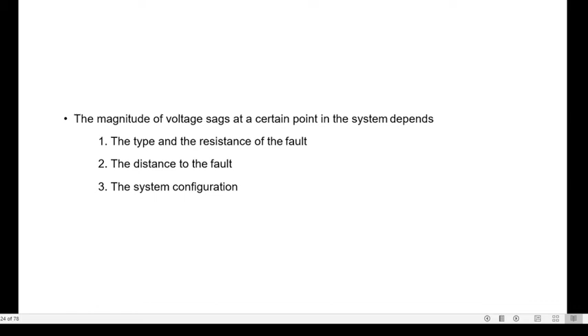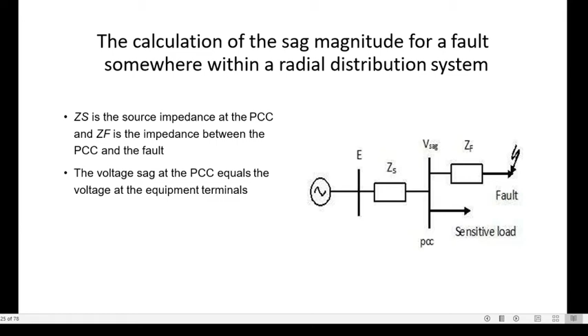So now the calculation of the sag magnitude for a fault somewhere within a radial distribution system. This diagram shows the radial distribution system with source EMF and system impedance. Voltage sag occurs on one line due to the fault at the point of common coupling. ZS is the source impedance at the PCC, the point of common coupling, and ZF is the impedance between the point of common coupling and the fault. So ZF is the fault impedance, ZS is the system impedance, and these two are interconnected with the help of the PCC, also referred to as the bus bar. The voltage sag at the PCC equals the voltage at the equipment terminal.